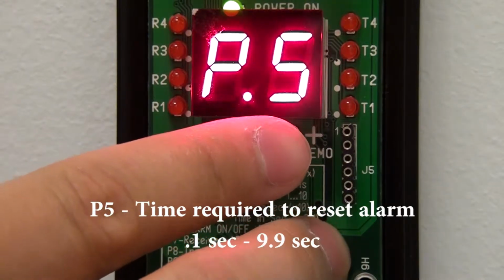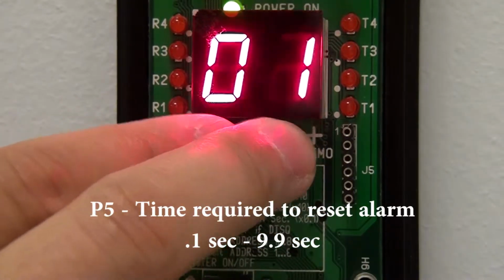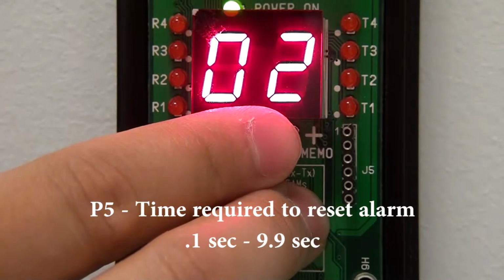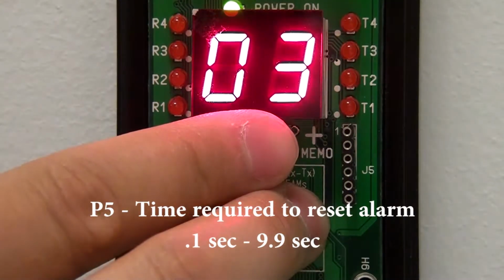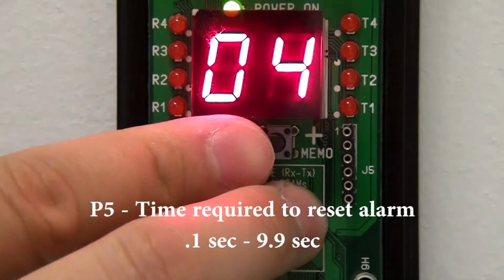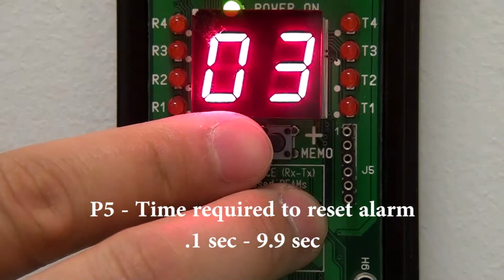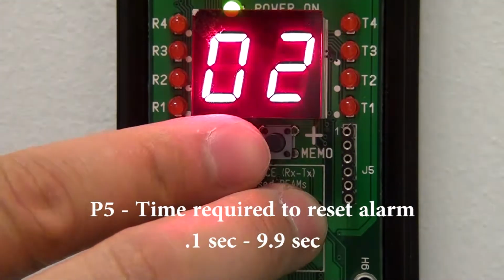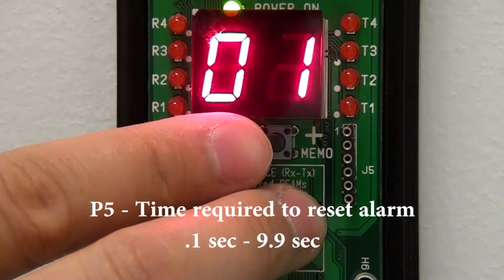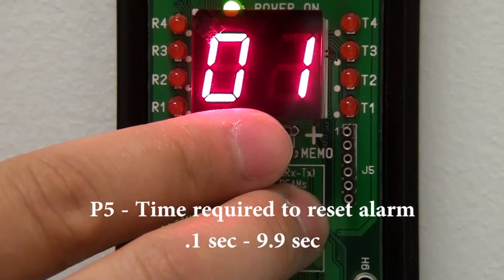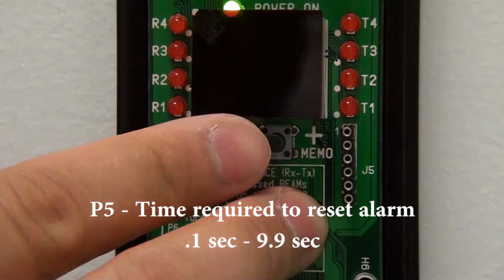P5 is the amount of time required before the alarm resets. So once the alarm trips, how long would you like to wait, in 1/10 of a second? So 1 will be 1/10 of a second, and 99 will be 9.9 seconds.